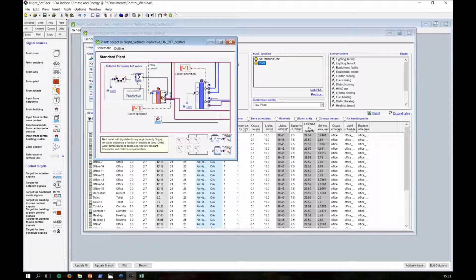Opening this macro controller, there are 2 conditions on this predictive control. The first one is using the rate of change of the temperature inside the building. I have a zone sensor here logged to all zones connected to the air handling unit, measuring the mean air temperature. I'm getting the minimum out of this, the worst case zone. I'm filtering the signal to smooth out noise, and then calculating the rate using the derivative module. This gives me how many degrees of change I have per second. On the other hand, I'm using the zone sensor to get a signal called time before use. This is a very special signal in IDA ICE that we also, I think, developed with Schneider Electric.